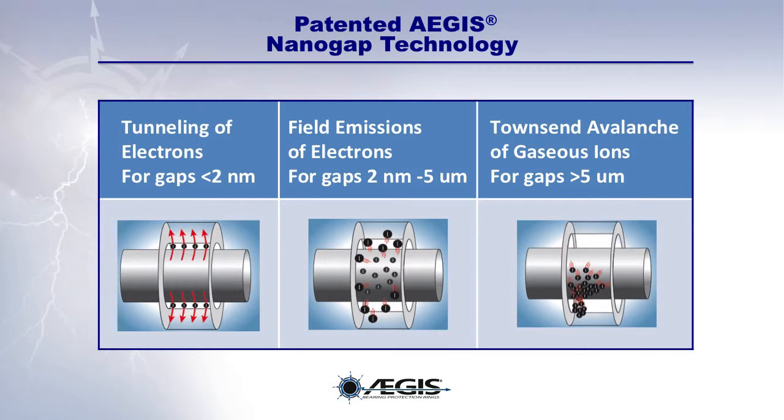The patented AEGIS nanogap technology ensures electrical contact, whether the microfibers are in physical contact with the motor shaft or merely in nanogap proximity to it. Through the three distinct nanogap processes shown here, AEGIS rings provide electrical contact with the motor shaft across gaps ranging from less than 2 nanometers to gaps greater than 5 micrometers.